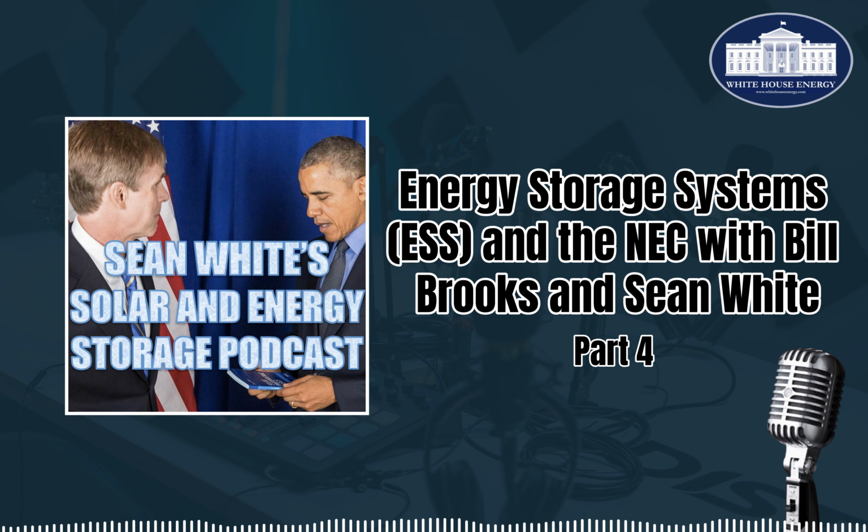Now with microinverters, as most of you are very familiar with, the Enphase microinverter, a lot of people use their little combiner panel, and that's a really handy unit because it's got the communications built into it and stuff like that. So a lot of people use that. So you don't see this kind of thing being done a lot with Enphase anymore just because it's common to be using those other tools that are from the manufacturer. I think some people get confused when they read the NEC and they think that it says that it all has to be only one breaker. Yeah. Each connection of source has to be on a breaker, but you can have multiple source connections.